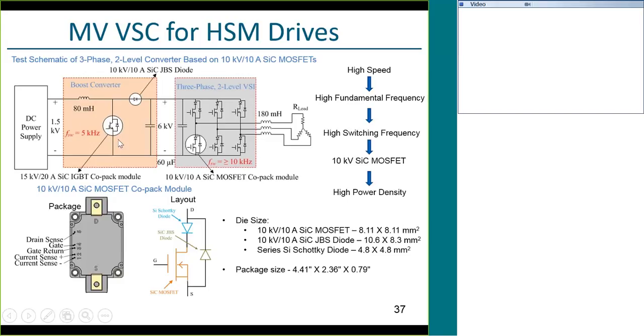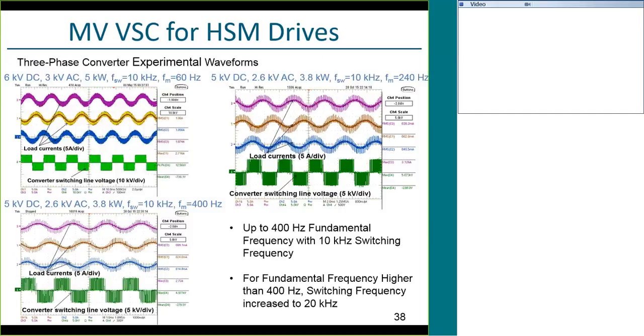We have a boost converter built with our 15 kV IGBTs, giving us a 10 kV DC bus, but in this case we went up to 6 kV DC bus. We wanted to operate this as a 3-phase 2-level converter and test what switching frequency we could reach, starting from 10 kilohertz.